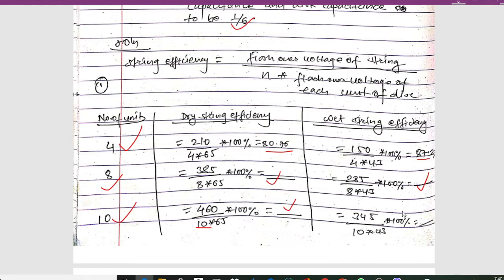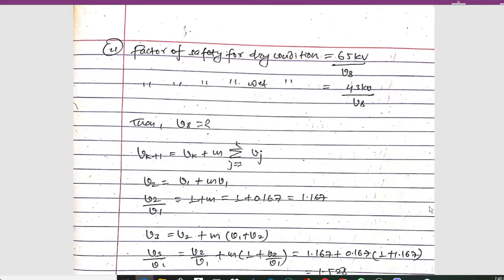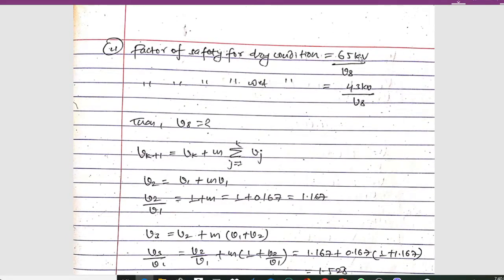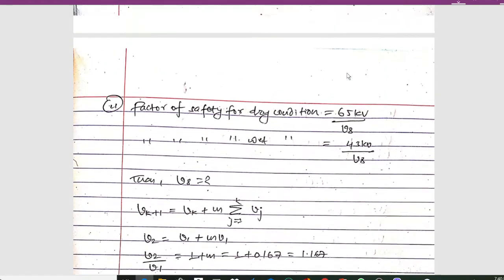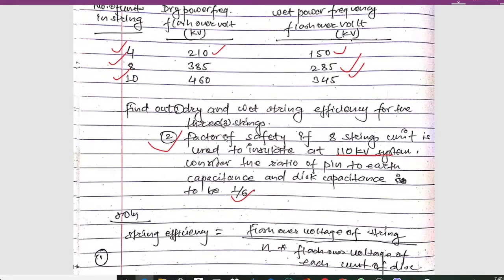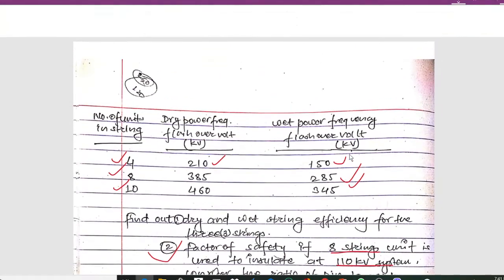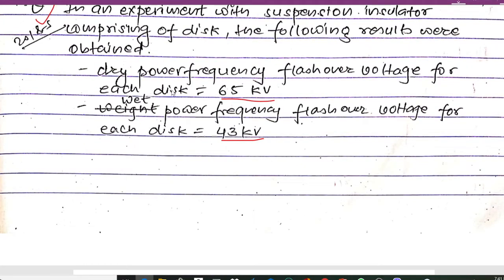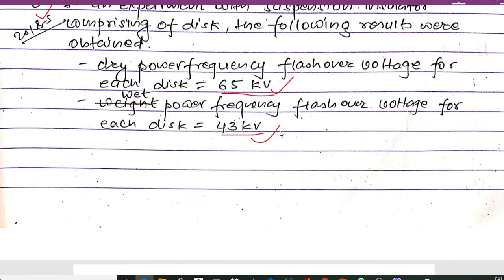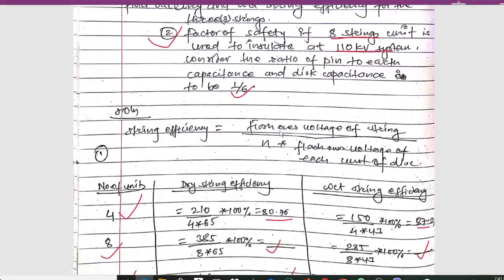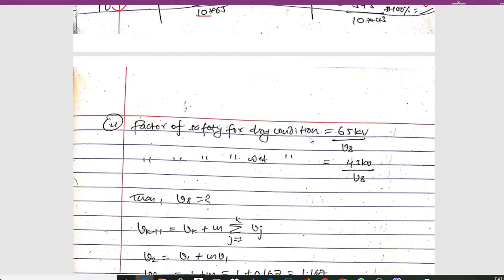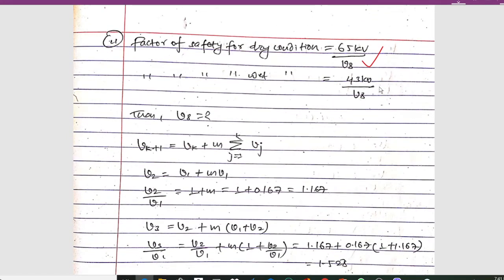The factor of safety is calculated as follows: for dry conditions, it is 65 kV divided by V8, and for wet conditions it is 43 kV divided by V8. Here, 8 strings are used to insulate a 110 kV system. The dry power frequency flashover voltage for each disk is 65 kV and the wet is 43 kV.